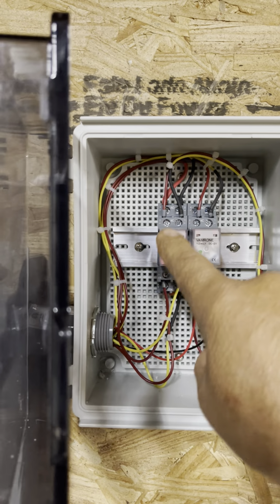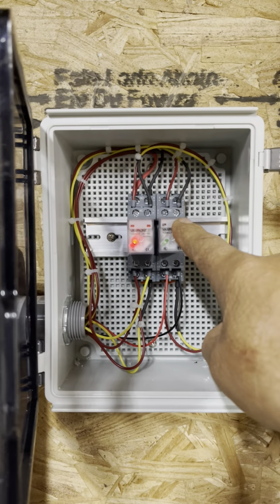When it switches over to the other side, it's going to take its feed from this relay. This relay has a 12-volt coil, and under normal circumstances, that coil is triggered by the XP6000s. When they don't have a battery need, it's not on. I took a voltage feed from the XP6000 panel, brought it in and put it here. And then there is an open side of that relay. So what happens? The grid fails. The Generac under normal circumstances would start and say, I need to run the generator. Well, now it senses that I'm still getting voltage from the inverters, and so it doesn't start.